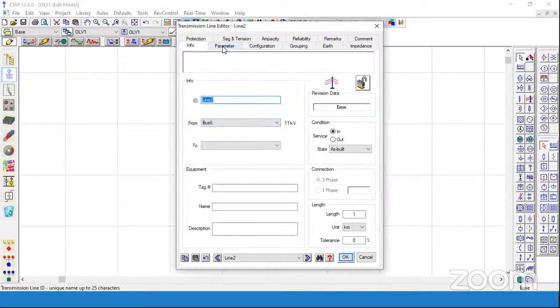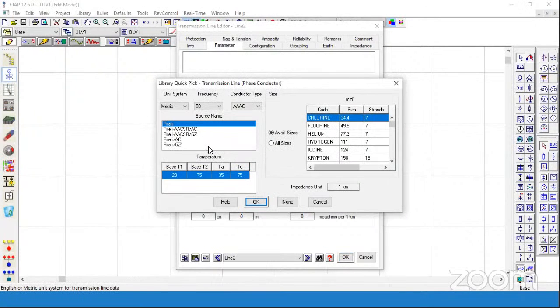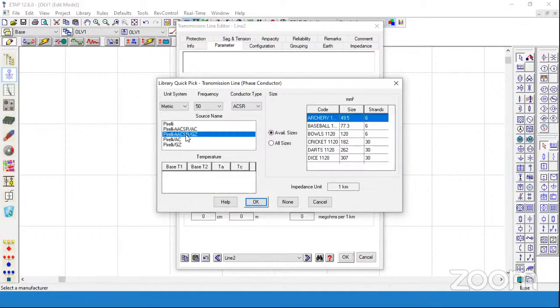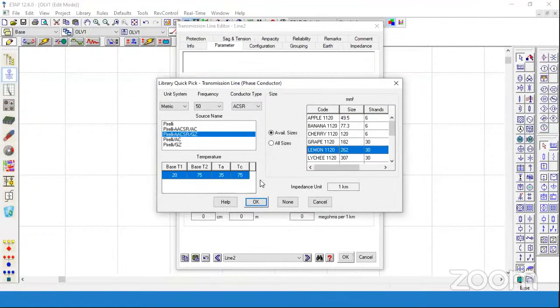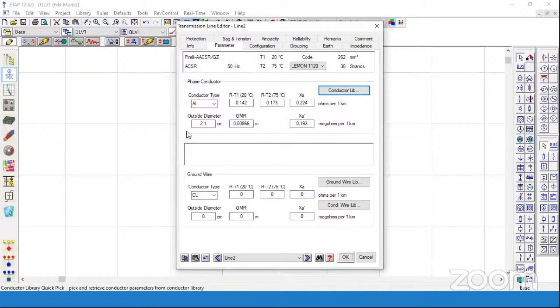Then I will model the transmission line. Here in this parameter section, different types of conductors have been listed in ETAP. We will go with one of them: there are zebra conductors, wolf conductors, panther conductors, dog conductors, lemon conductors, and orange conductors. So let's go with the lemon conductor. Here in this library, let's select the lemon conductor. With this, all the parameters of the lemon conductor will be fetched from this library. We don't need to input any parameters. ETAP has all the details of these conductors.